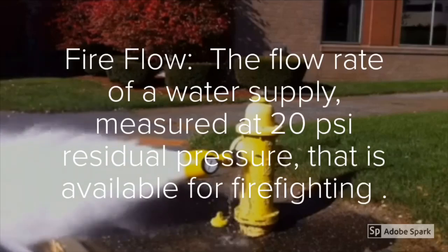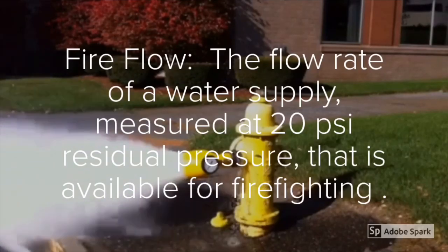The residual pressure criterion of 20 psi is used because it is the minimum pressure recommended for fire engine use by water authorities in order to minimize the possibility of creating a negative pressure in the water main and the resulting damage to the water supply system.